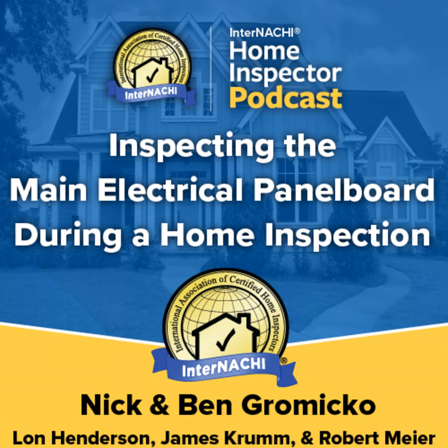Where branch circuit wiring in a residential building is modified, replaced, or extended, the branch circuit should be protected with AFCI and GFCI protection. GFCIs and AFCIs must be installed in readily accessible locations because they have test buttons that should be pushed periodically. Manufacturers recommend that homeowners and inspectors test or cycle the breakers and receptacles periodically to help ensure that the electrical components are working properly.